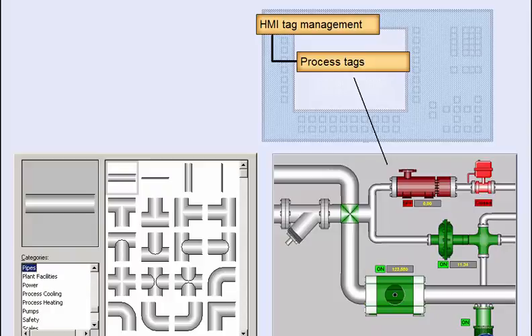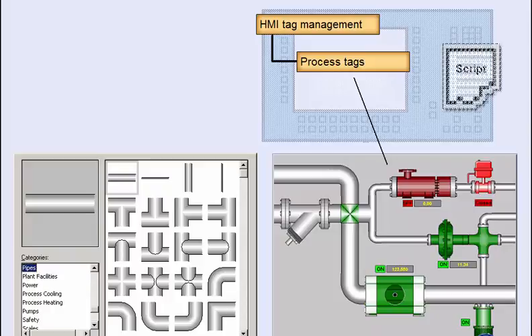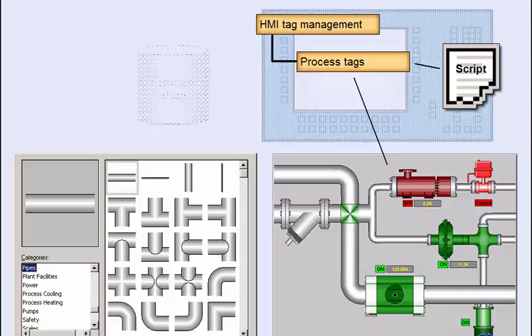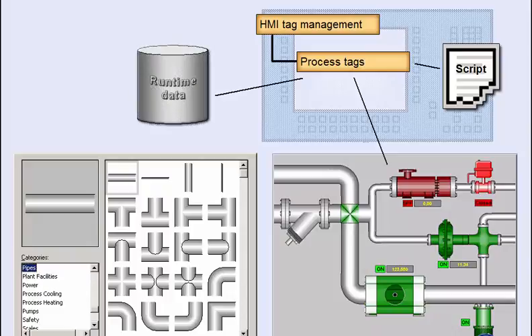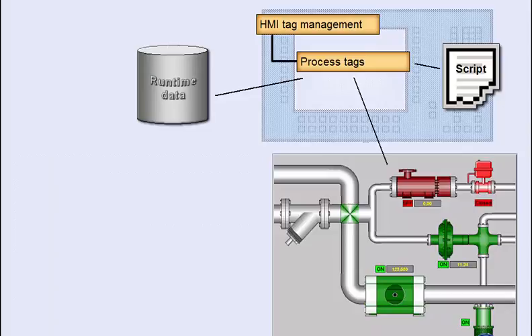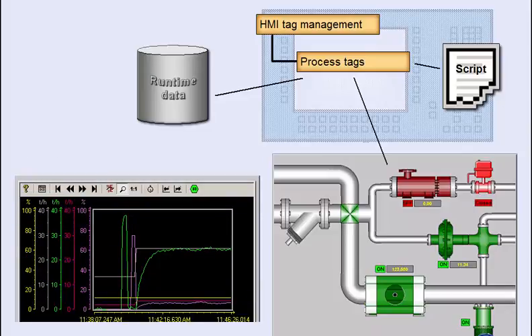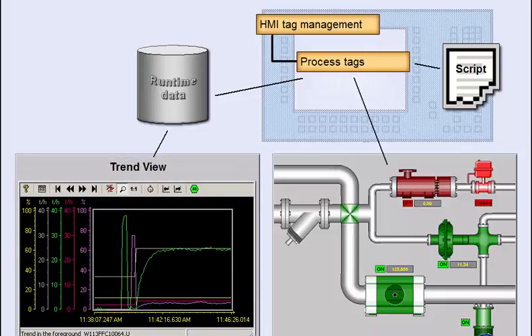Objects are dynamized by links with tags and used for visualization of the process and for operator control. The tags can also be pre-processed in scripts. For instance, logical combinations and arithmetic calculations can be performed. Event-triggered or cyclic archiving of tags is possible to track process value histories. Once tracked, the sequence of process values can be output in graph or table form.